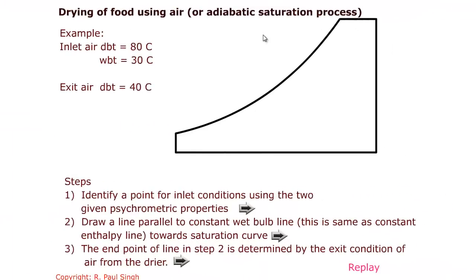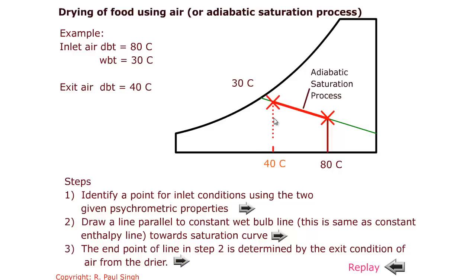Let's look at adiabatic saturation. Inlet air is at 80 degrees C dry bulb and wet bulb temperature of 30 degrees C, and exit air is at 40 degrees C. We identify a point with dry bulb temperature of 80°C and 30°C wet bulb, then follow the constant enthalpy line to the 40 degrees C dry bulb temperature. Thus we have identified the process with inlet conditions of 80°C dry bulb and 30°C wet bulb, going down to a lower dry bulb temperature of 40°C.